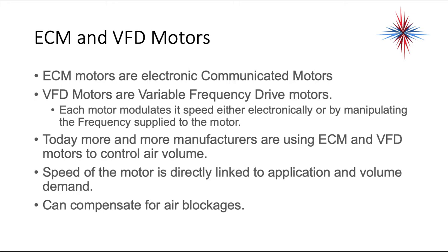The speed of the motor is directly linked to the application and volume demand. It can compensate to a point for air blockages — the motor is going to speed up and try to overcome air blockages, dirty filters, and incompatible ductwork. But at the same time, it can try to speed up too much and cause pretty high power bills and put a lot of wear on the equipment if things are not proper.